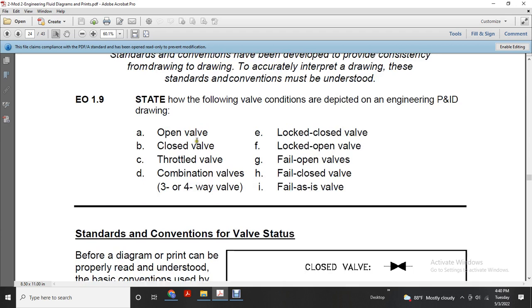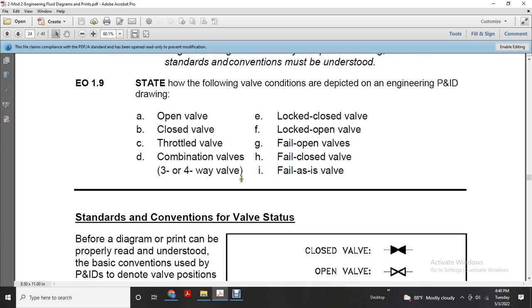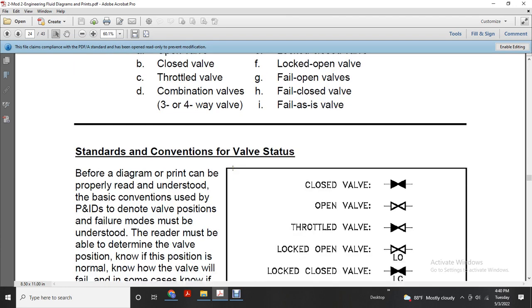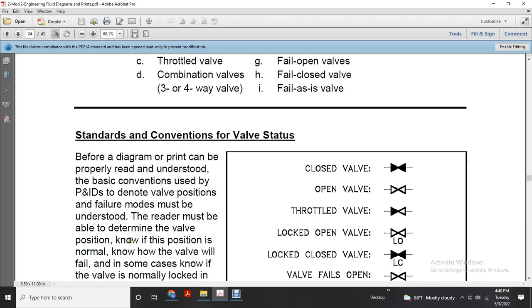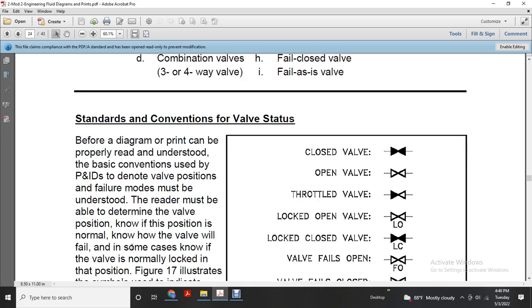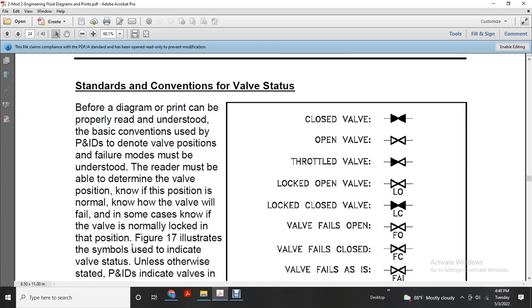Standard symbols show open and closed valves, and combination valves: 3-way, 4-way, locked closed, locked open, fail closed, fail as is. The standard convention for valves must be understood before a diagram can be properly read. Understand the basic conventions of the piping and instrument drawing used to denote valve position. Valve failure modes must be understood, and the reader must be able to determine the valve position, know the normal position, and know how the valve will fail in some cases, such as a valve normally locked in position.